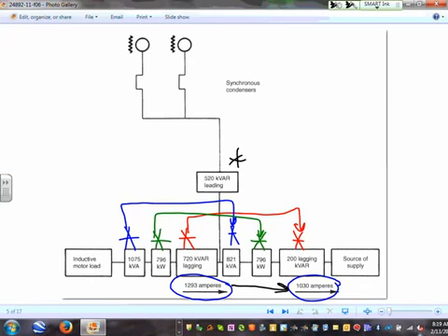Voltage drop will become better when you reduce the current for the same amount of power, for the same amount of load that I need. I'm pulling 1030 amps versus before I was pulling 1293. That's why Xcel gets mad at you. All you need is 1030 amps, but you're paying for this, since you're still making it give you this amount of amps. So remember, correcting the power factor is good for voltage drop, good for the conductor, good for Xcel or your company.